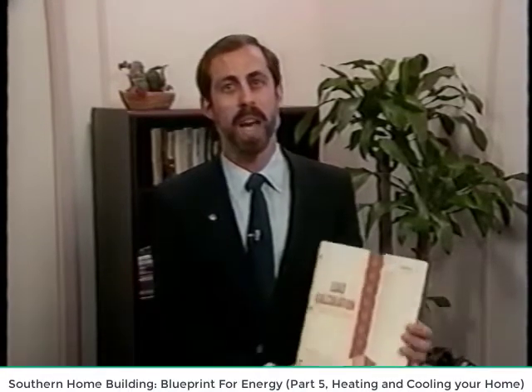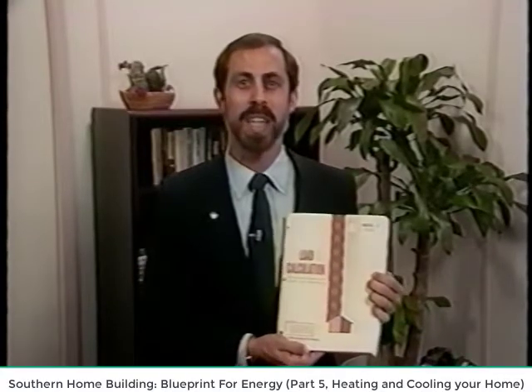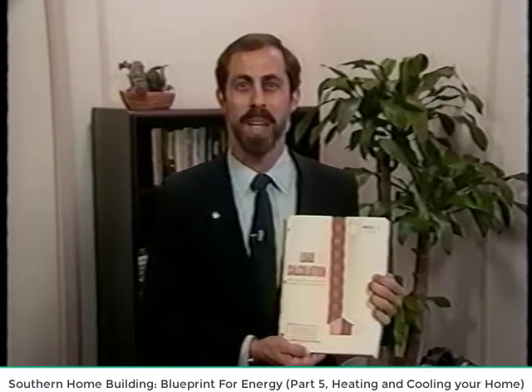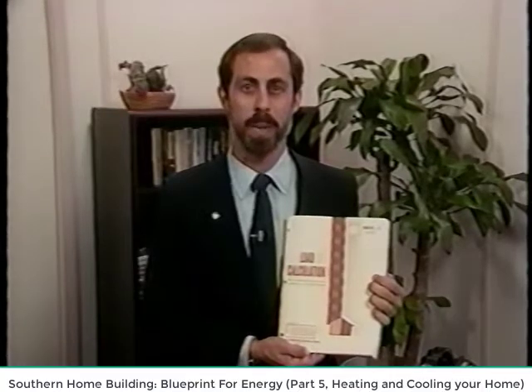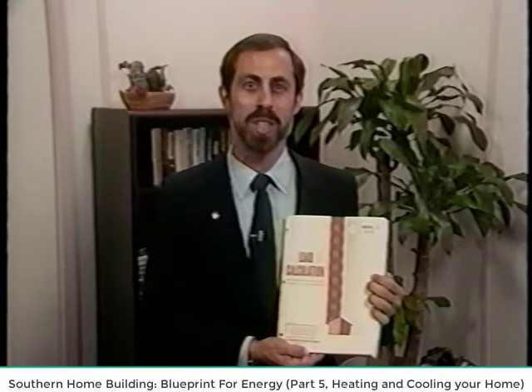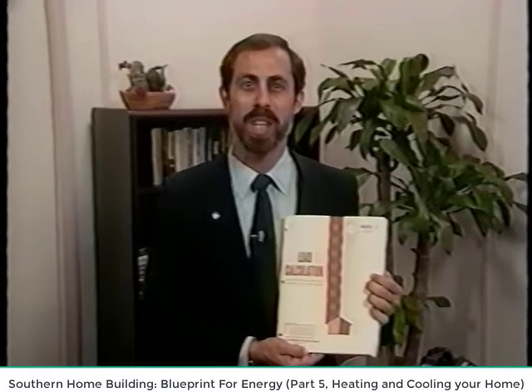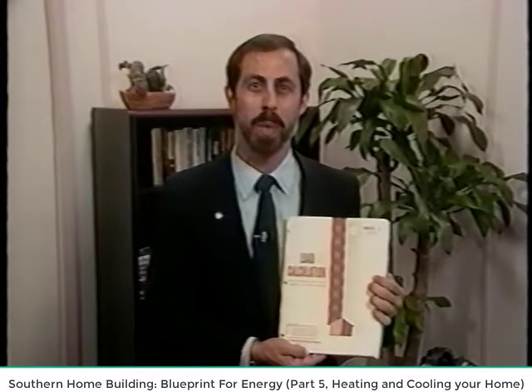Before we begin with one of the most prevalent problems in choosing heating and cooling equipment, proper equipment sizing, you will need to know what a Manual J calculation is. Manual J is the name of the highly regarded heat loss, heat gain calculation developed by the Air Conditioning Contractors of America. The Manual J calculation is generally accepted as the industry standard for calculating the correct size of residential heating and cooling equipment. Now that you know what a Manual J calculation is, let's find out more about it in our program.